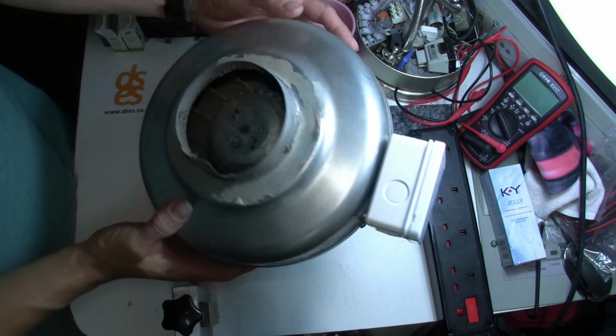The alarm is because when the IR test stops as I release the test button, the Robin is no longer putting out a voltage, which matches the charge in the capacitor. Indeed, the probe's dropped to 0 volts. So we now have a potential difference between the charged capacitor at 280 odd volts and the tester at 0 volts. The capacitor then discharges back into the tester.